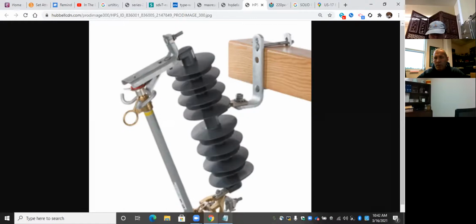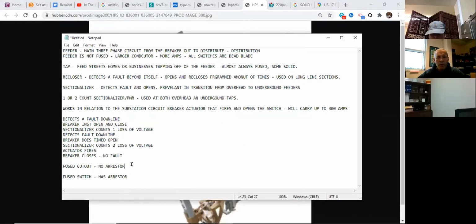All right, so as far as fuse cutout and fused switch, both of them, what is their purpose? Obviously, by the word fused, what are they intended to do if there's a fault detected beyond the fuse? Blow the fuse. All right, blow fuse. There's very little technology going on here, if any at all, as far as the fuse in the switch is concerned. It does have to coordinate with all the rest of the equipment, but all it's supposed to do is blow the fuse. Fault occurs, blow the fuse - same on this one, fault occurs, blow the fuse on the fuse switch or the fuse cutout.